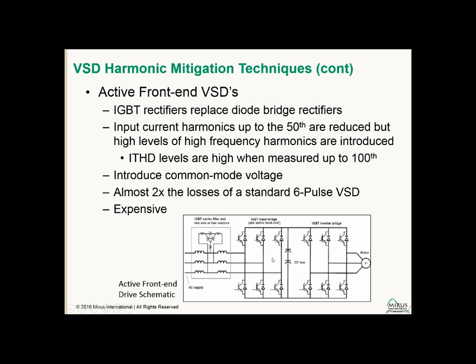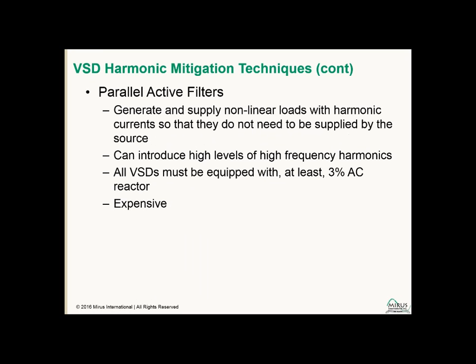The fact that there's a second inverter section typically will double the losses of the VSD because most of the losses in a variable speed drive are related to the inverter section. So if we're doubling the inverter section, we're going to essentially double the losses. And of course they are an expensive solution. And then the final option here that we'll throw out there is a parallel active filter. These generate and supply nonlinear loads with harmonic currents that are essentially out of phase. They supply the load so that the source doesn't have to supply the harmonic content, thereby reducing the current distortion being drawn.